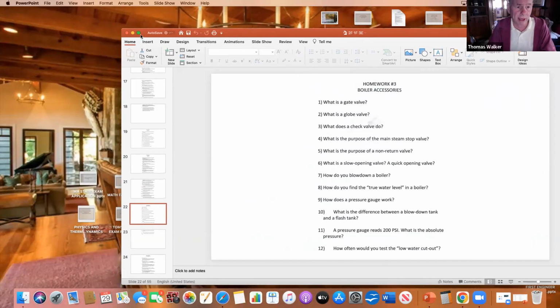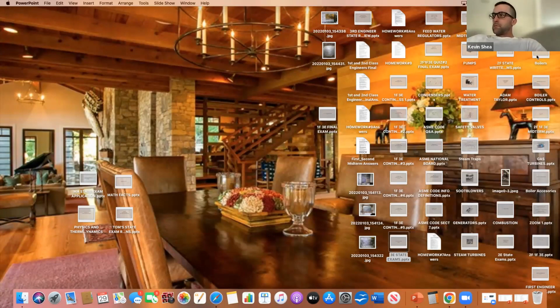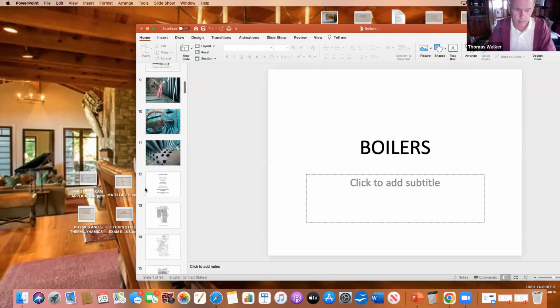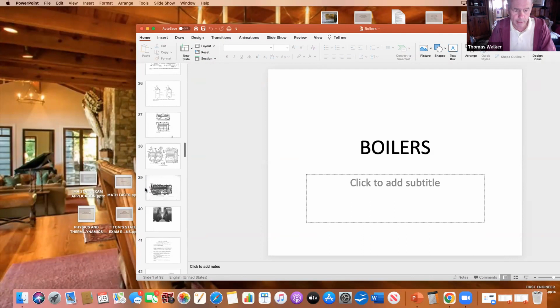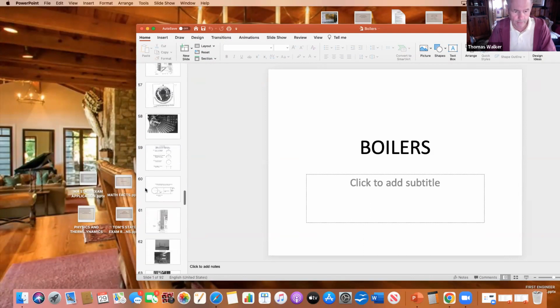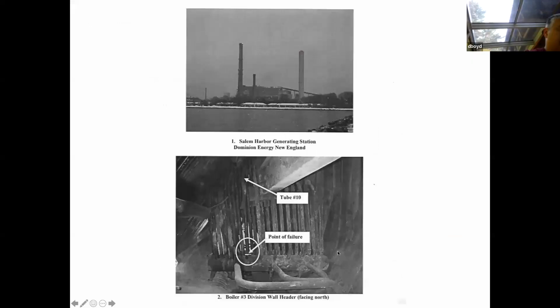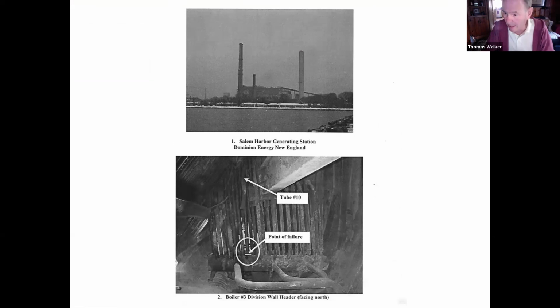Remember we talked about that boiler at Salem Harbor? Let me show you what I'm talking about here. Just bear with me one second. If you look closely at this picture, this piece of pipe right here, the large diameter pipe, these tubes are what we call water wall tubes. They come down into a header, a place where they all gather together. And off of that, there'll be lines that have blowdown valves on them. They are used exclusively to drain the boiler.